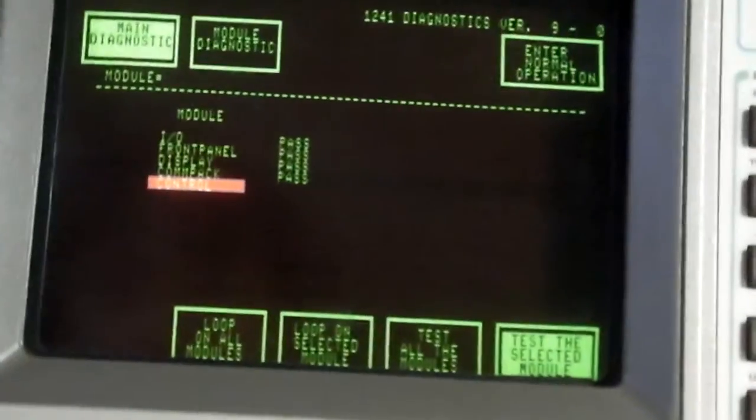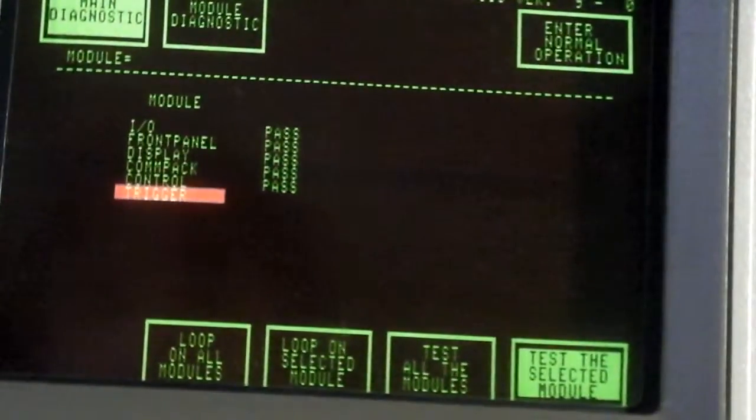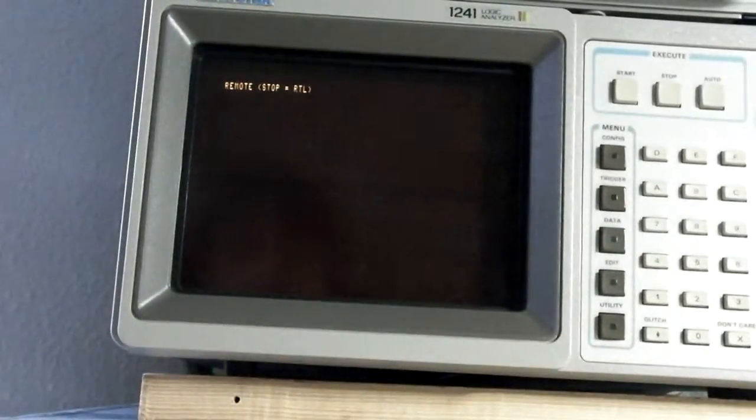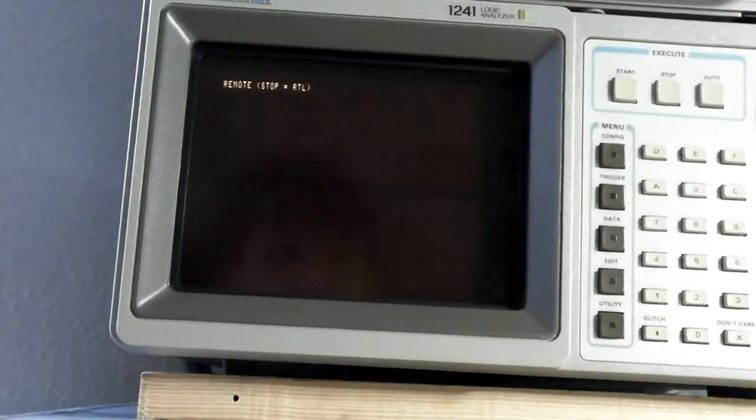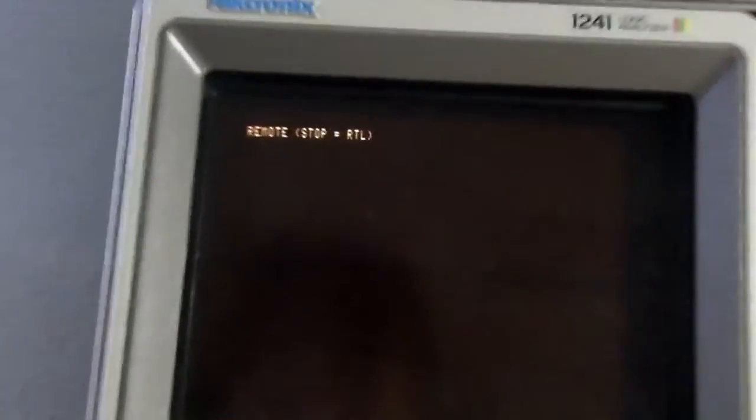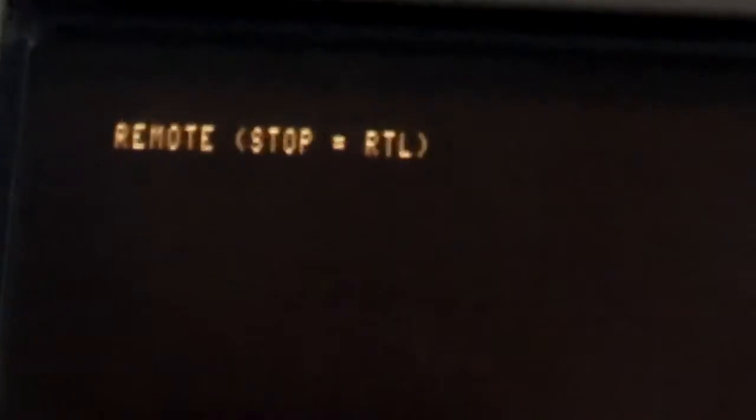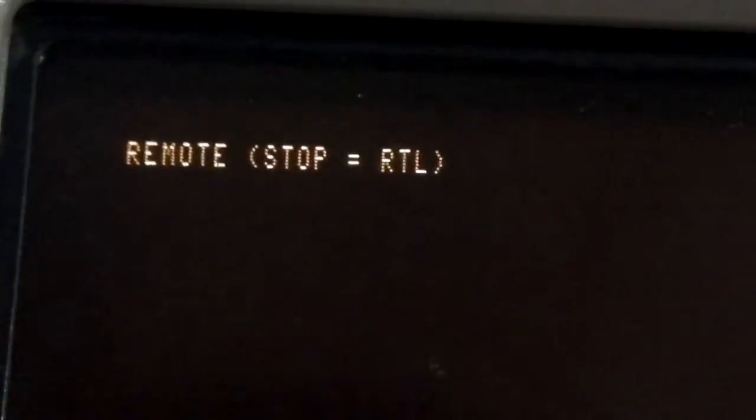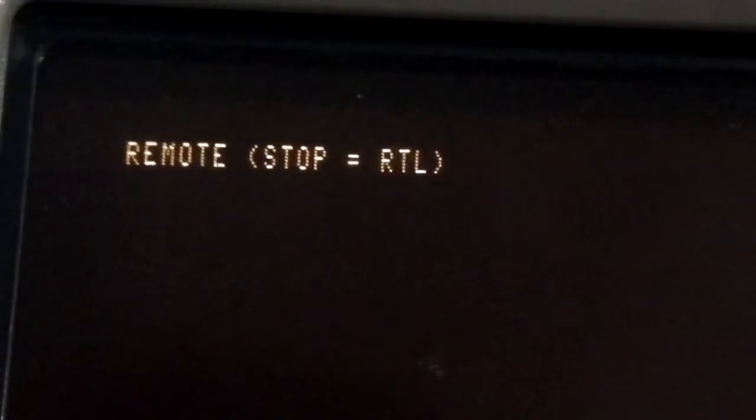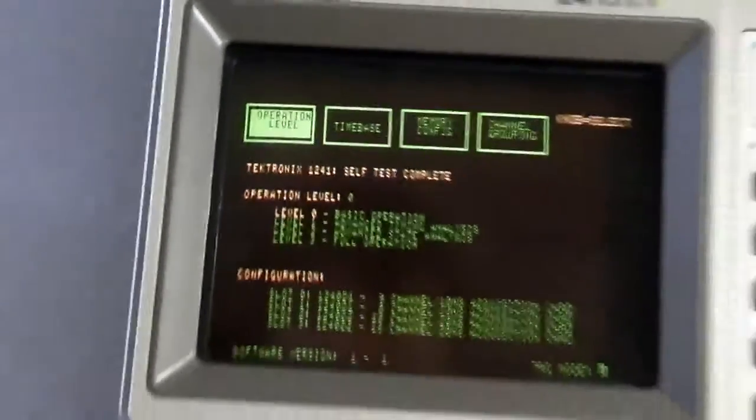Okay, now I will switch on the 1241. Wait for finishing of the self test. Okay, we are through. And I already switched on the GPIB controller. And the 1241 has noticed that it's connected to a GPIB controller and goes to some kind of remote mode. But we are able to interrupt this remote mode by pressing the stop key.